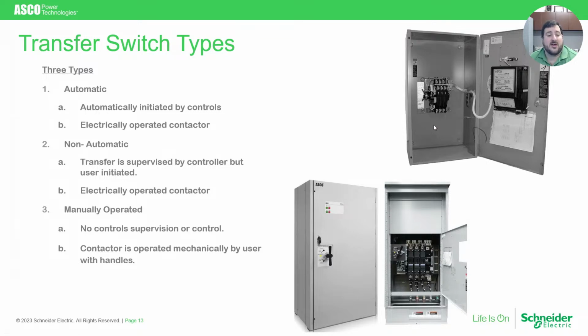Alternatively, there's also non-automatic transfer switches, which still have a controller, but require a user to initiate the transfer. These units are still electrically operated, meaning the contactor does not have to be manually driven, but a user must initiate the control.